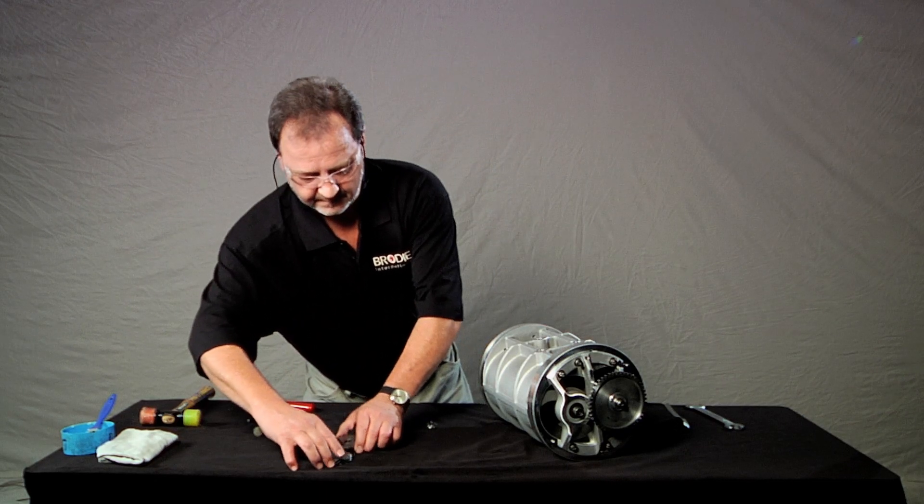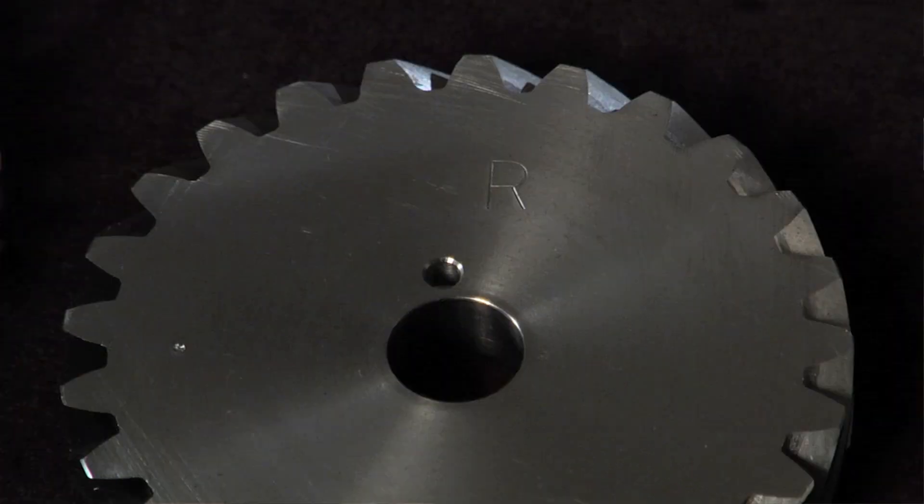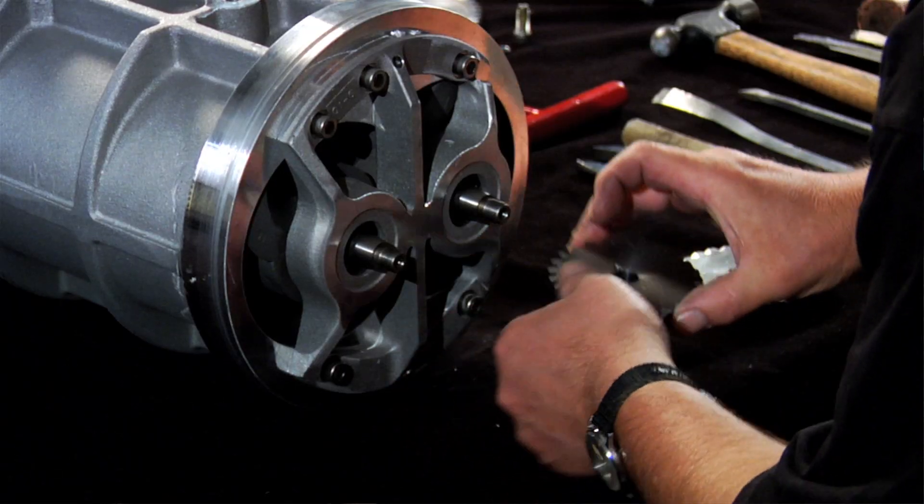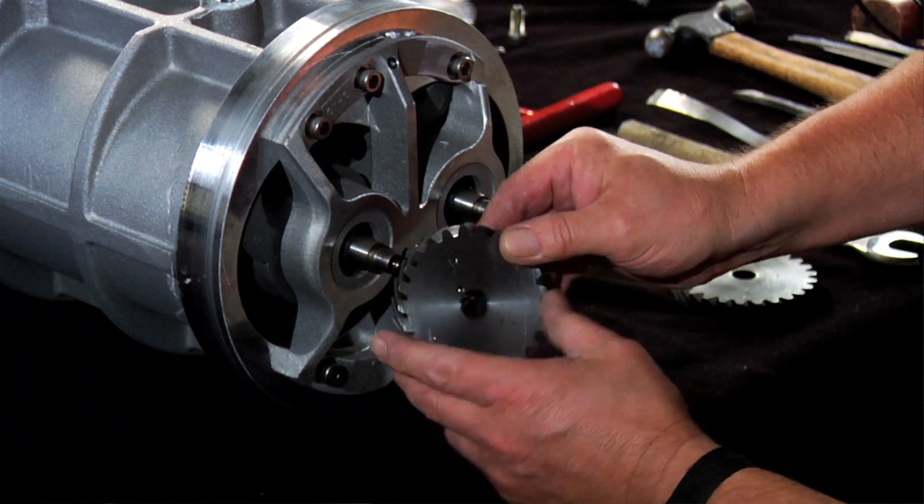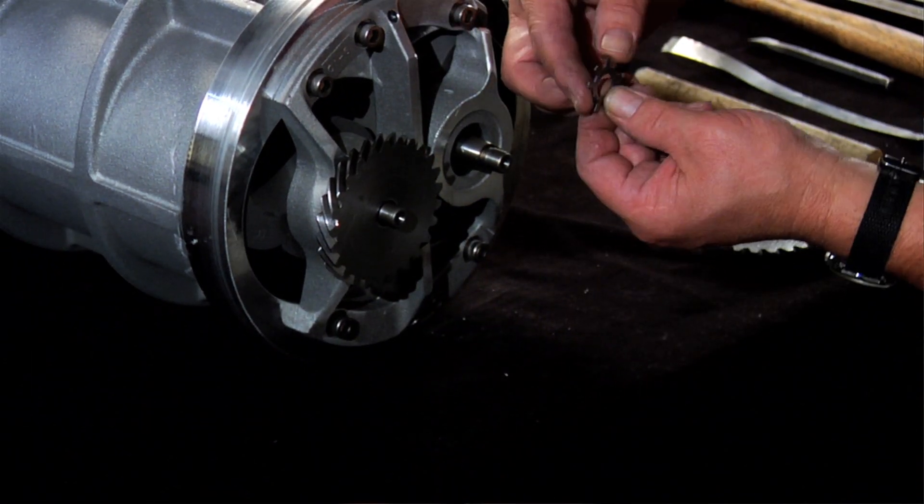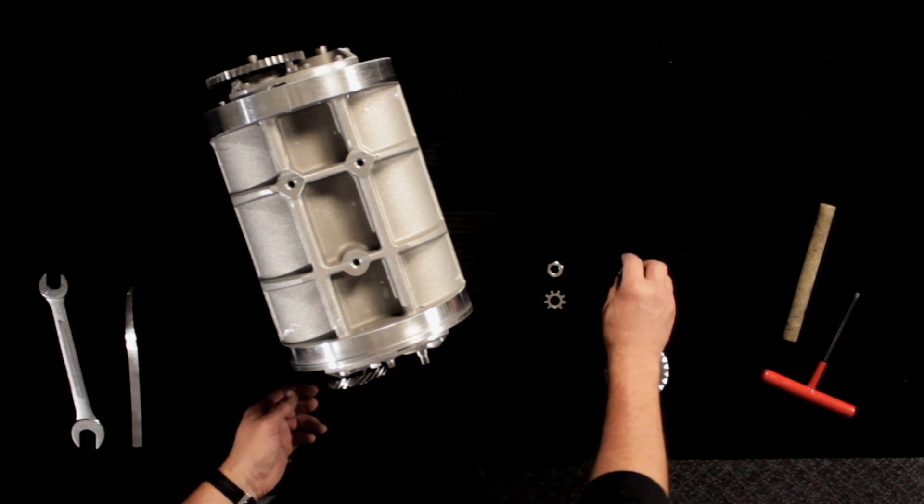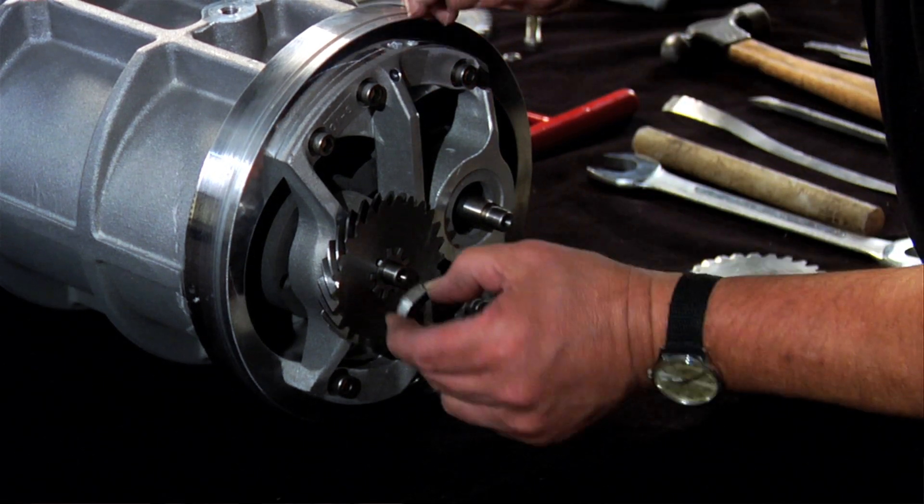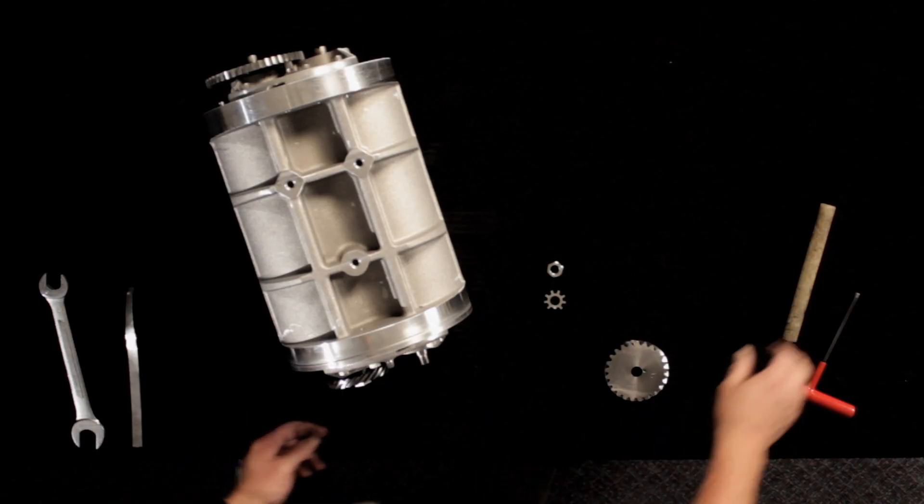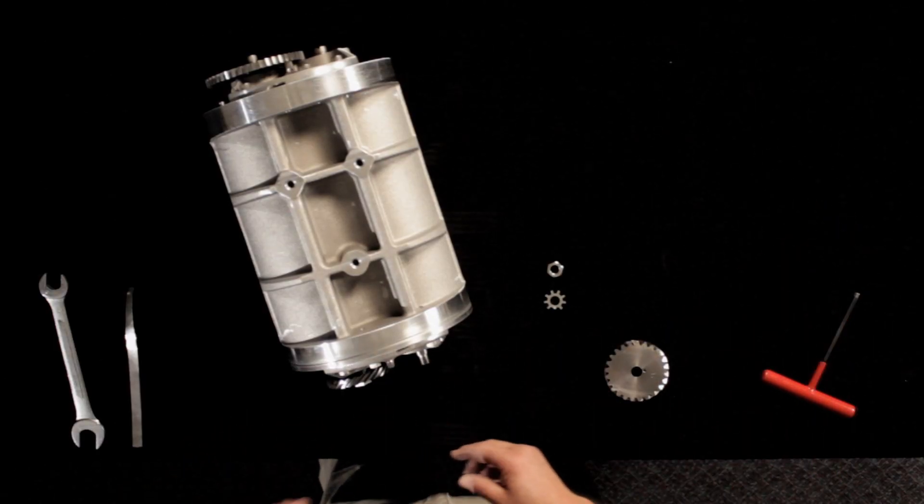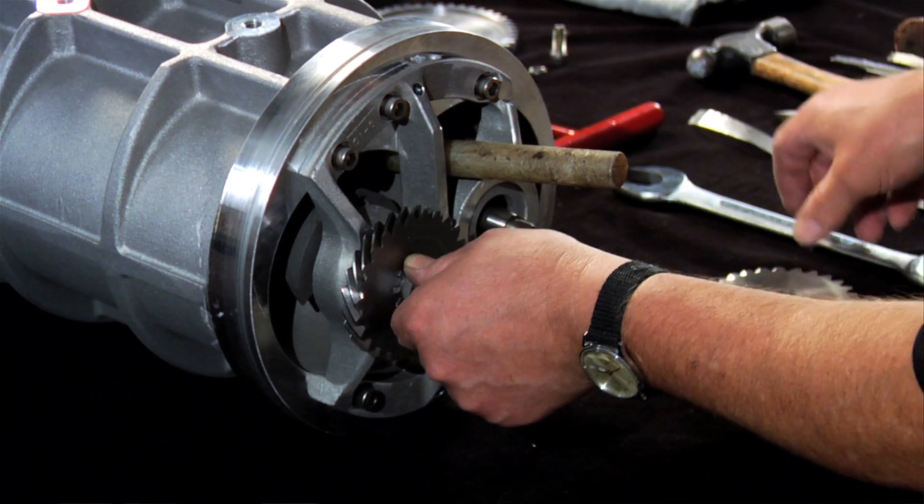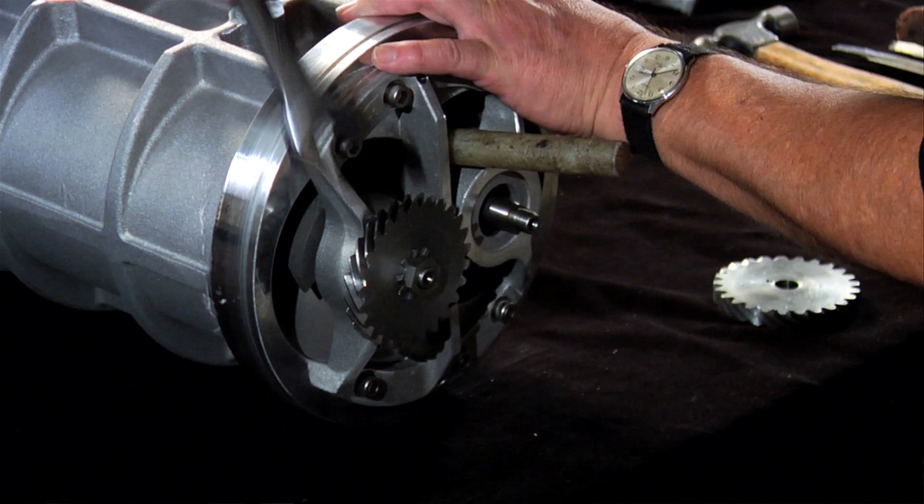Return to the front of the unit and match the timing gears to their corresponding rotors. Note that the pulse output gear is attached to the right-hand rotor in the back. The timing gear teeth are sharp, so please be careful. Install the right timing gear. Place the locking ring over the shaft. Install the lock nut with the rounded shoulder toward the measuring unit. Again, lock the rotors with the blocking stick and tighten the lock nut with your wrench. Be sure to tighten this gear.